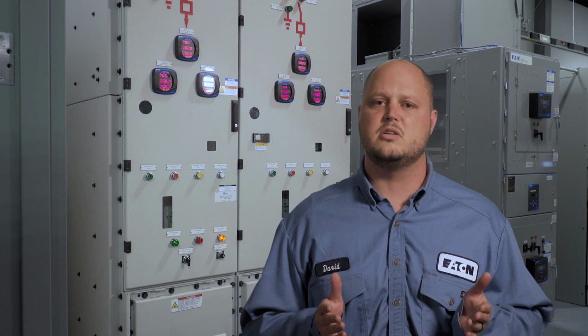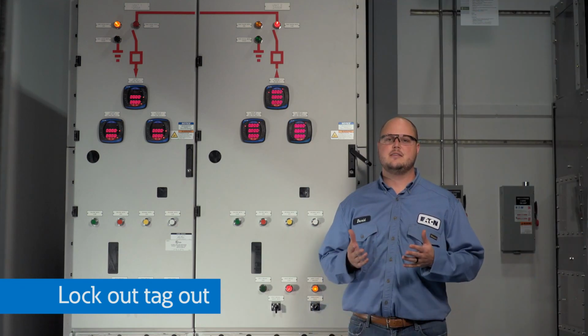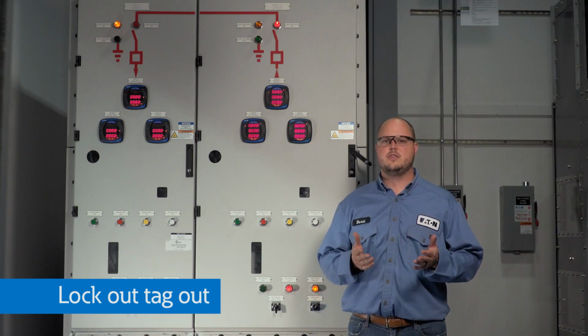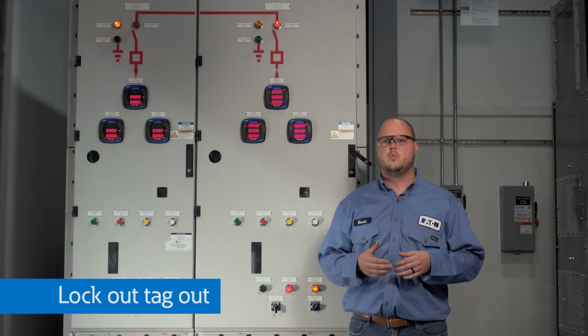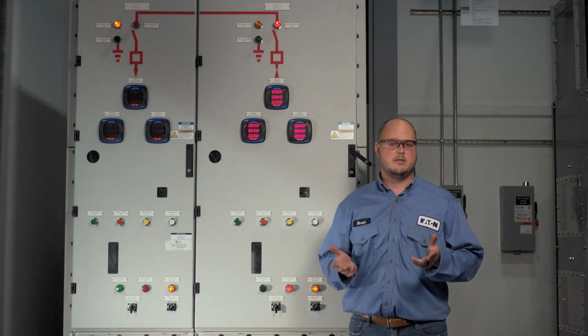to ground. For fixed mount circuit breakers, which are most common in the IEC markets, and for gas insulated switchgear, which always uses the fixed mount circuit breakers, the circuit is isolated and/or grounded through the use of isolation switches and ground switches or 3-position disconnector switches. Let us discuss the lockout-tagout procedures for the xgis switchgear, which are used in potential maintenance scenarios.